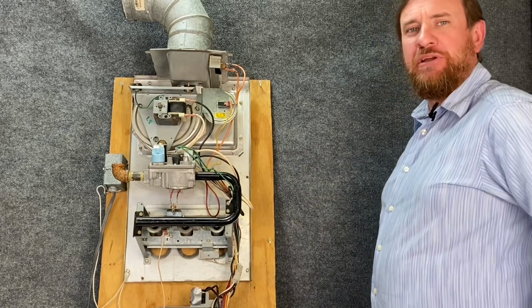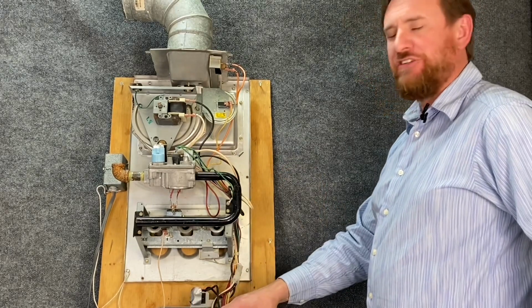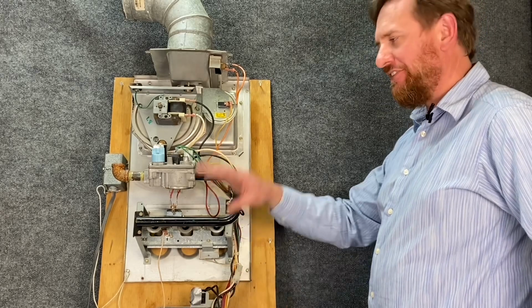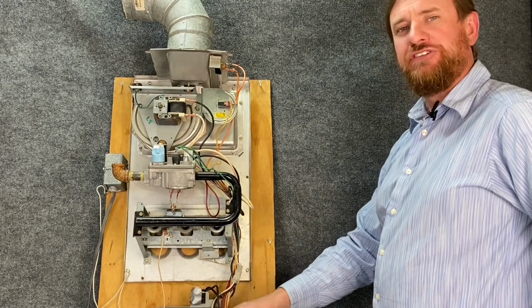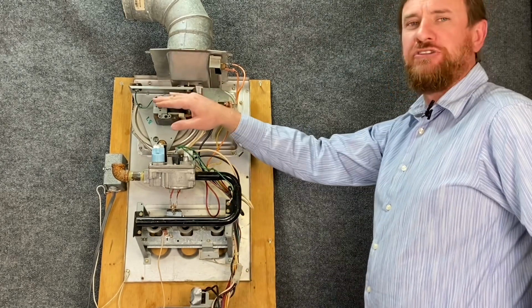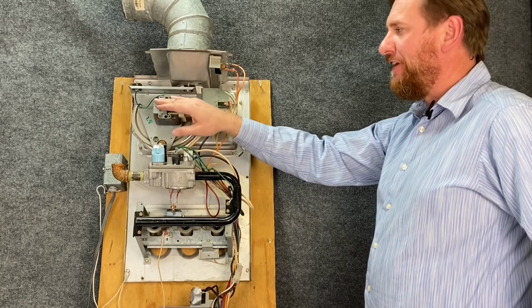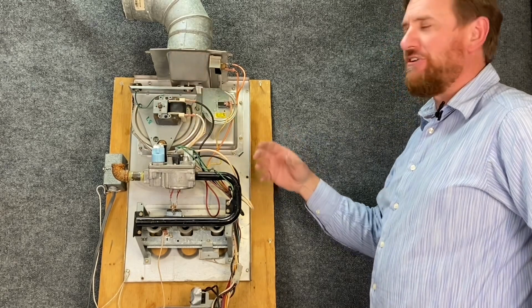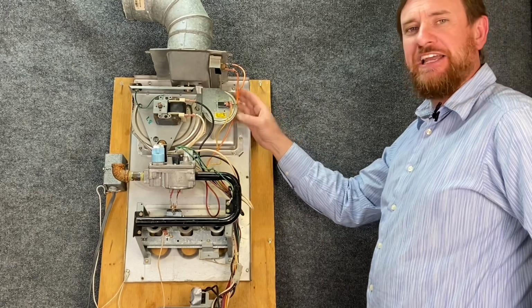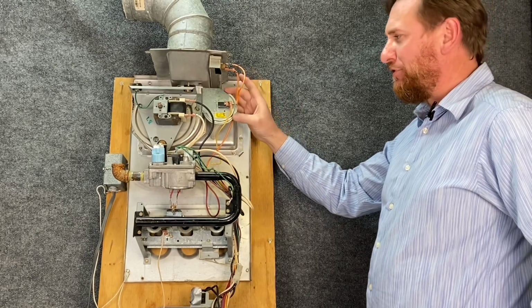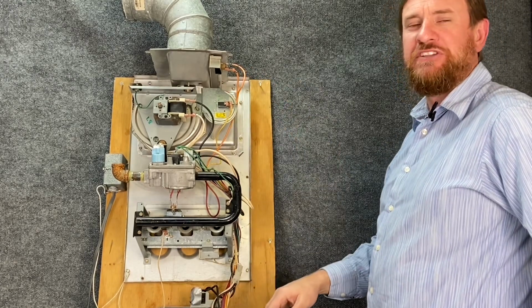The sequence of operation: the thermostat calls for heat and sends 24 volts to the IFC. The IFC does a safety check, then closes a relay and sends 120 volts to our inducer fan motor. The inducer fan motor pulls a draft through the heat exchanger. It also pulls a vacuum to our pressure switch. Our pressure switch closes and sends 24 volts to the IFC.